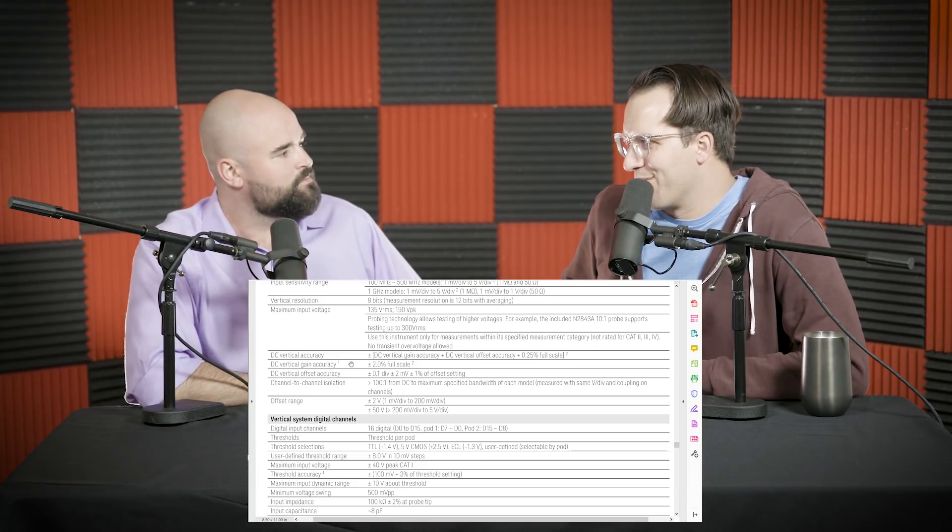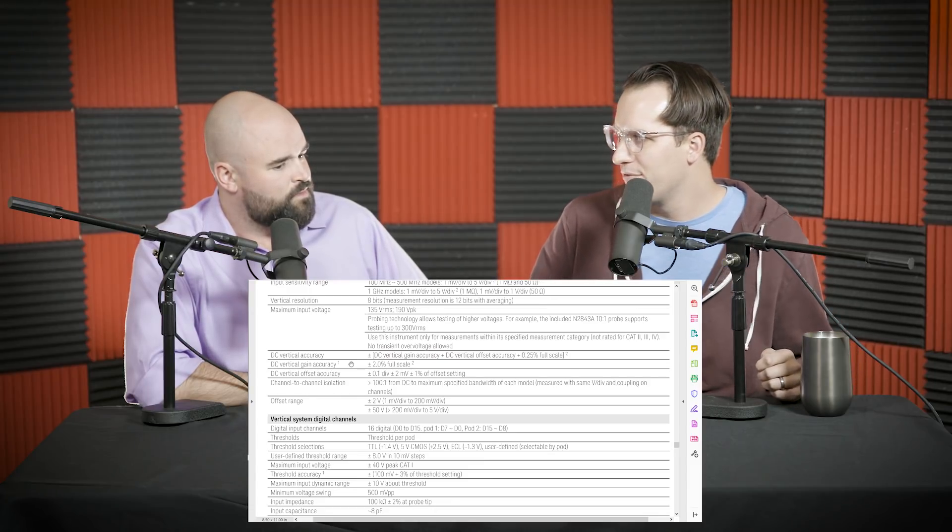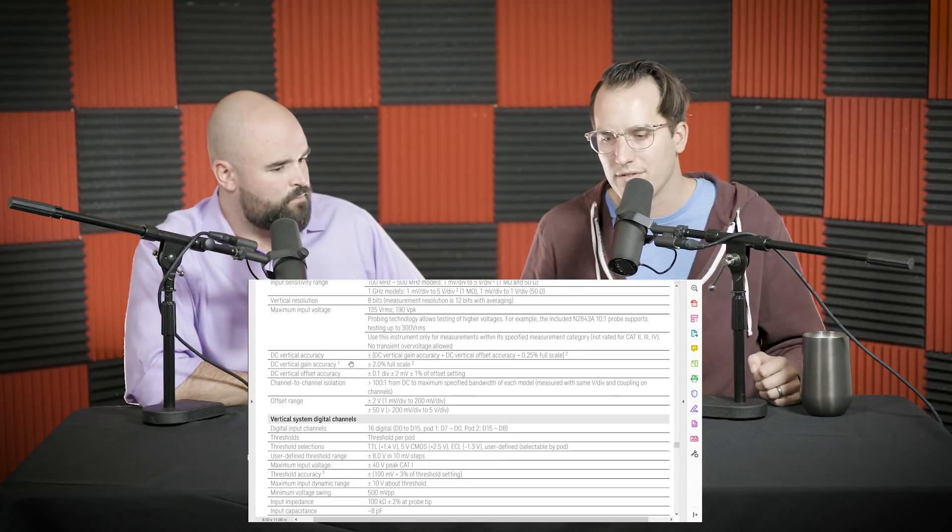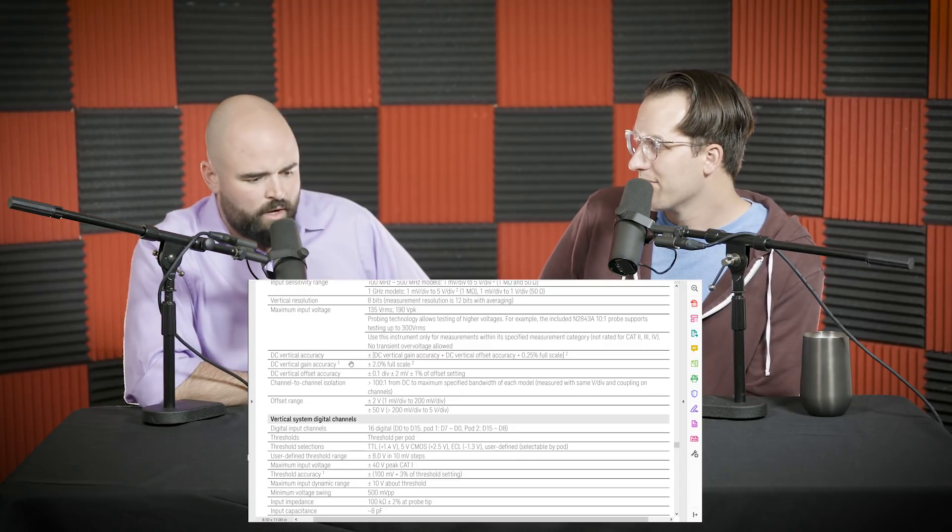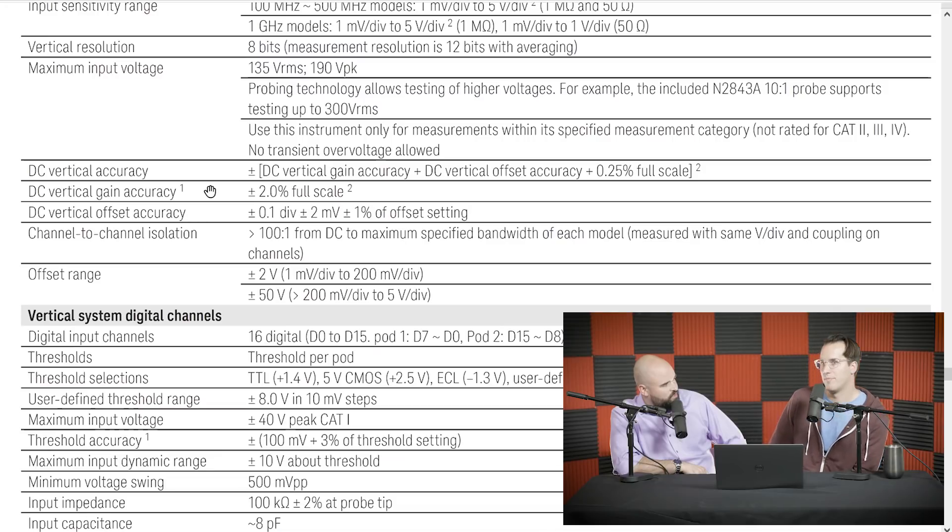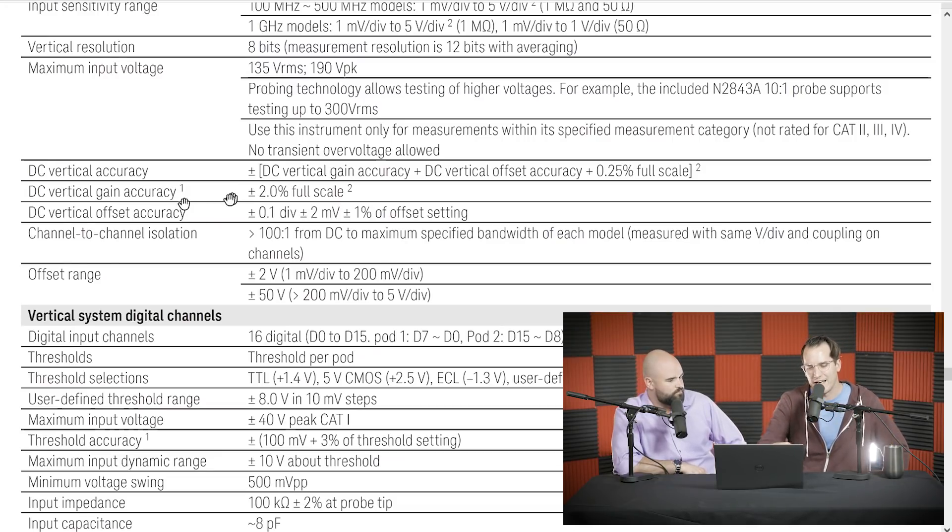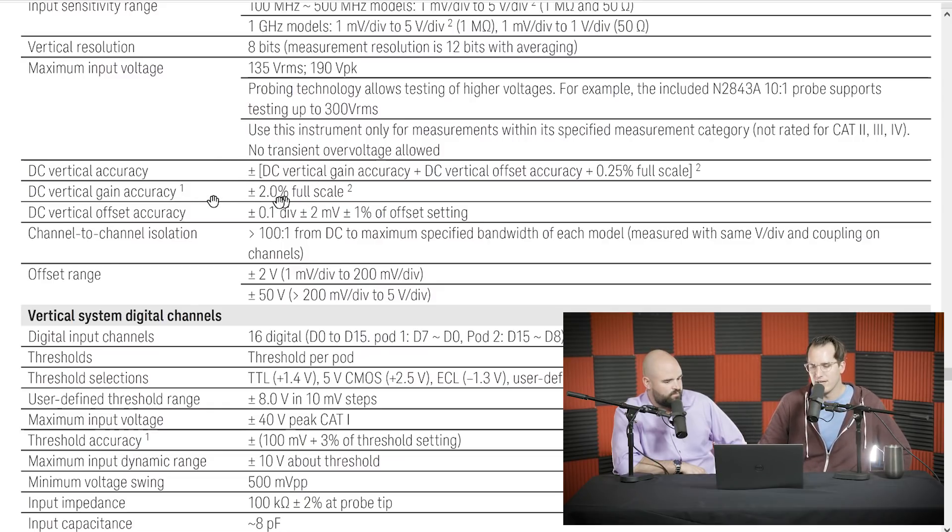Accuracy is a really interesting topic to think about in a data sheet. I'm just gonna throw caution to the wind and say this: Oscilloscope vendors don't specify accuracy for AC signals. We have frequency response, we have to stay within the three dB range and there's a whole flatness thing and you can get plots often. But when we're going to spec accuracy, we spec DC accuracy.